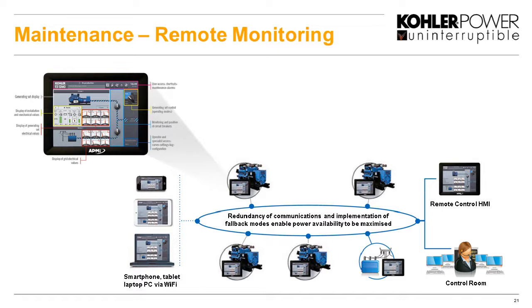It can be used to do an automatic test on a weekly or monthly basis. And if there's any issues with that, it will alert someone. And that's the important thing, that someone is alerted. And that will allow any problems to be highlighted before you actually have an outage and you need this standby set to work.